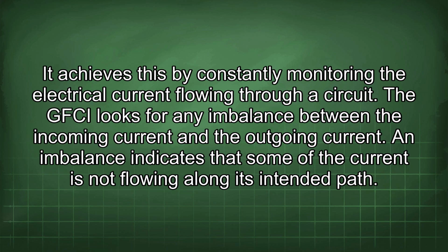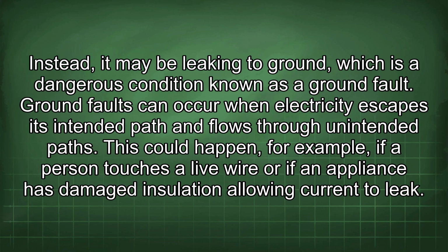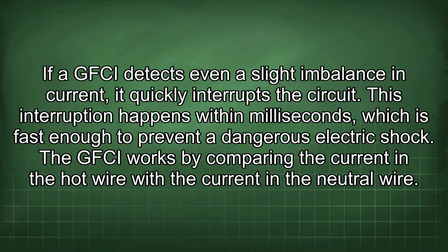The GFCI looks for any imbalance between the incoming current and the outgoing current. An imbalance indicates that some of the current is not flowing along its intended path. Instead, it may be leaking to ground, which is a dangerous condition known as a ground fault. Ground faults can occur when electricity escapes its intended path and flows through unintended paths. This could happen, for example, if a person touches a live wire or if an appliance has damaged insulation allowing current to leak. If a GFCI detects even a slight imbalance in current, it quickly interrupts the circuit. This interruption happens within milliseconds, which is fast enough to prevent a dangerous electric shock.